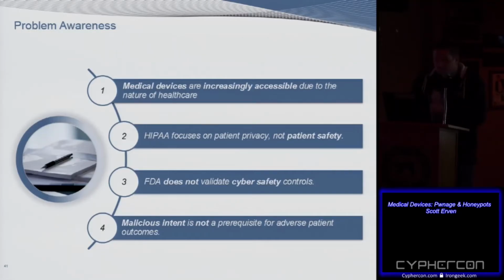The third one: the FDA does not validate cyber safety controls. To be further clear on that, the FDA has done a lot. I'm going to talk about some of their progress on the next slide. But the FDA does not independently validate cyber safety or security controls of that device prior to it getting 510K or pre-market approval. So that does not happen. And fourthly, like I said before, it's really important to understand that it's not just malicious intent that can result in an adverse patient safety issue, right? But there is risk there.